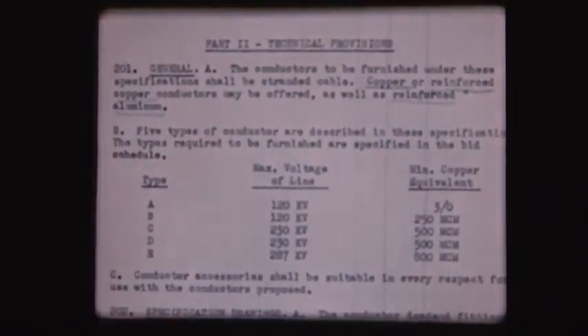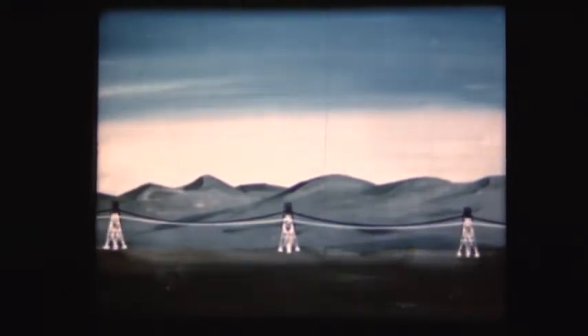What does all this mean in terms of practical transmission line design and construction? In transmission design, one of our considerations is providing the necessary clearance between the conductor and the ground, or other obstructions over which the line must pass. It is only reasonable that a conductor which is stronger, or lighter, or both, can be drawn up to a lower sag and still keep the strain within safe limits. This means that with a stronger or lighter conductor, we can use lower towers or longer spans, in either case affecting substantial economies. Elimination of one steel tower can mean a saving of as much as $10,000.